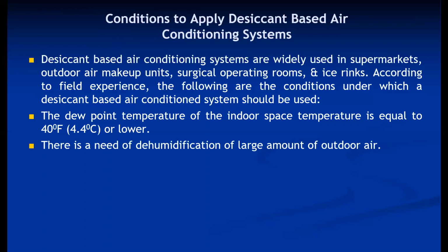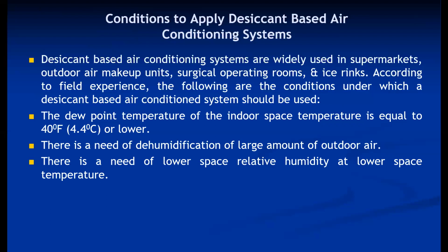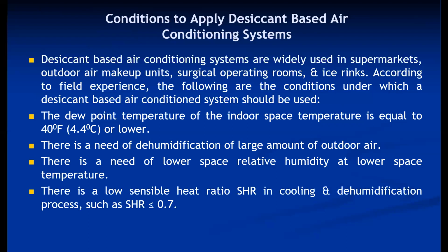If there is a need for dehumidification of a large amount of outdoor air, then this system is beneficial. If there is a need for lower space relative humidity at lower space temperature, that is, when the space humidity requirement is low, then this desiccant based air conditioning system is beneficial. And if the sensible heat factor is less than 0.7, that means the sensible heat contribution is less, and our latent heat contribution is more, in that case it is advantageous.